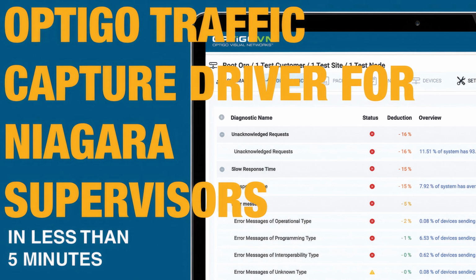Setting up the Optigo Traffic Capture Driver for supervisor upload mode is for Niagara stations that don't have a direct internet connection and can't upload capture files directly to Optigo VN on their own. In this mode, a supervisor acts as the intermediary. The station captures traffic locally and holds the files, while the supervisor checks in, collects the captured files, and uploads them to your Optigo VN account on the station's behalf.